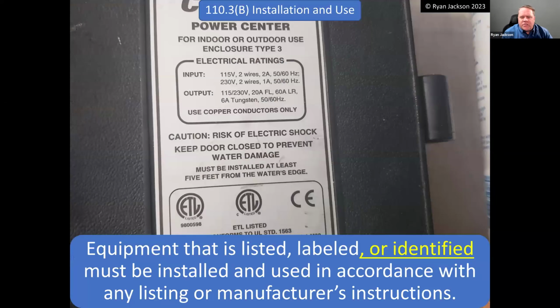110.3(B) is a pretty simple section now. For years, it said equipment that's listed or labeled has to be installed in accordance with the manufacturer's instructions. In the 2023, they made a change to say equipment that's listed or labeled or identified. And identified is a weird word in the NEC. I've got to be honest, I'm not in love with the definition. But basically, identified means that it's suitable for a specific application.